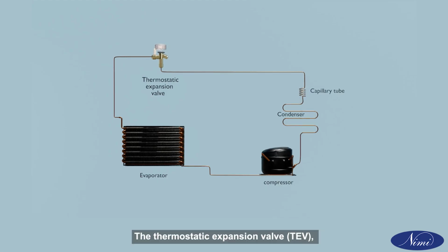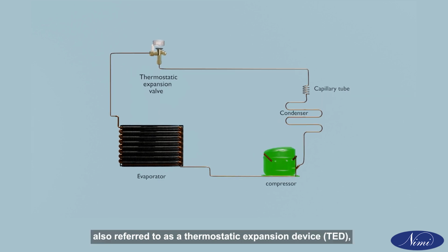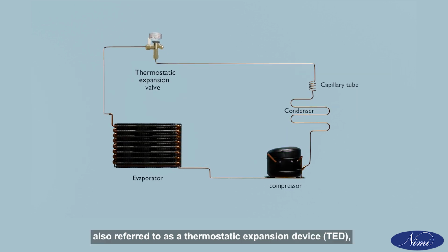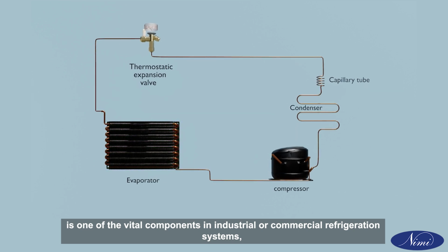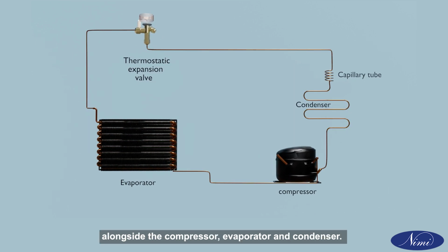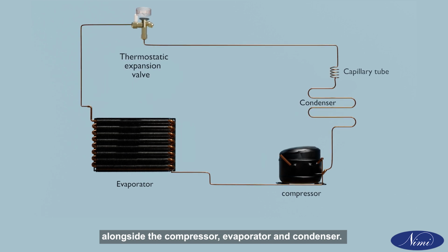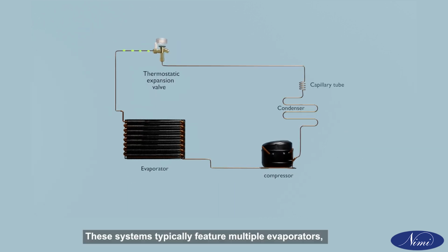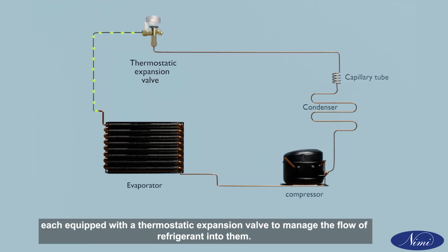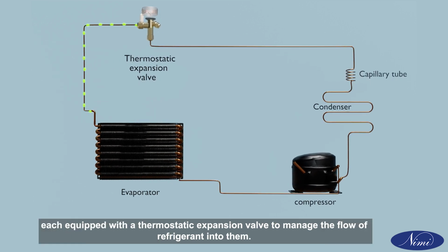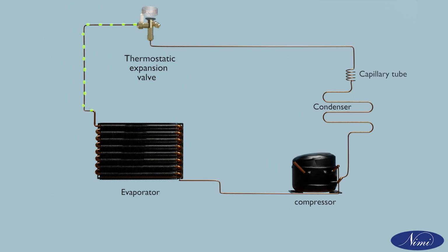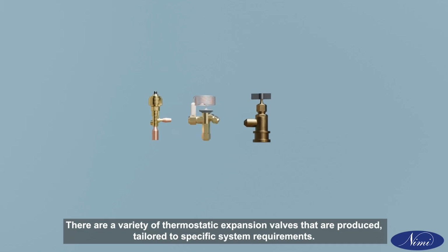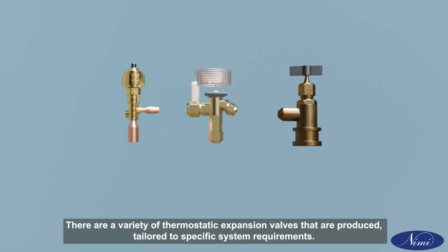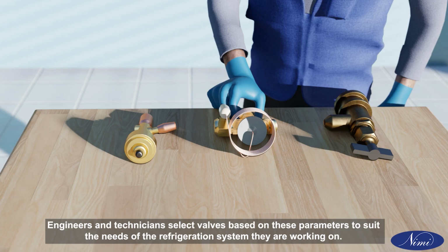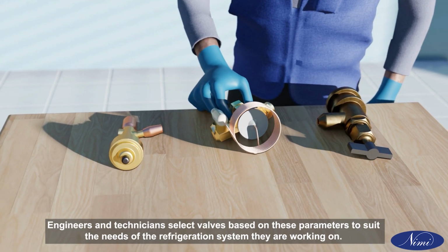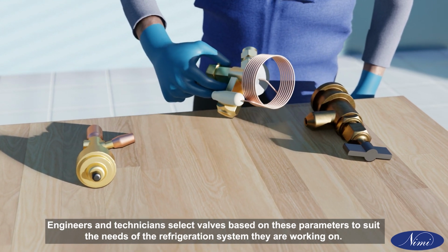The thermostatic expansion valve, TEV, also referred to as a thermostatic expansion device, TED, is one of the vital components in industrial or commercial refrigeration systems, alongside the compressor, evaporator, and condenser. These systems typically feature multiple evaporators, each equipped with a thermostatic expansion valve to manage the flow of refrigerant into them. There are a variety of thermostatic expansion valves that are produced, tailored to specific system requirements. Engineers and technicians select valves based on these parameters to suit the needs of the refrigeration system they are working on.